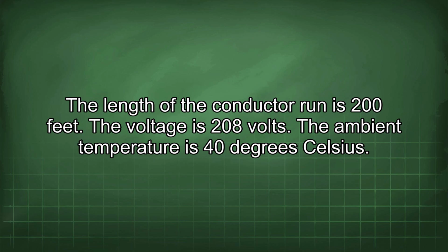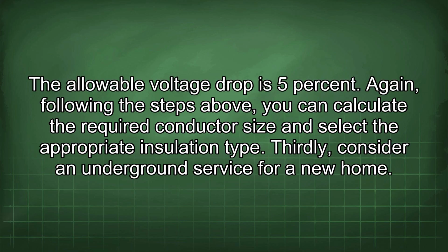The voltage is 208 volts. The ambient temperature is 40 degrees Celsius. The allowable voltage drop is 5%. Again, following the steps above, you can calculate the required conductor size and select the appropriate insulation type.